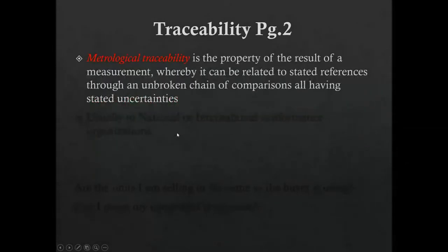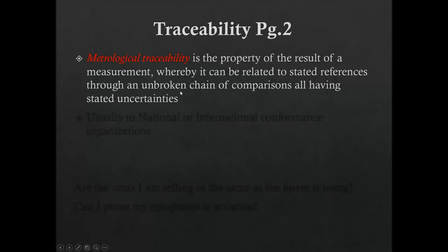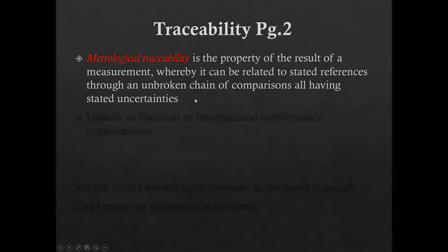What is traceability? Metrological traceability — 'metrological' being a European-style word for instrumentation or measurement — is the property of the result of a measurement whereby it can be related to stated references through an unbroken chain of comparisons, all having stated uncertainty. Basically, traceability is the result of calibration and calibration documentation that tells us how accurate a measurement is, all the way from your level up to some big governing body.